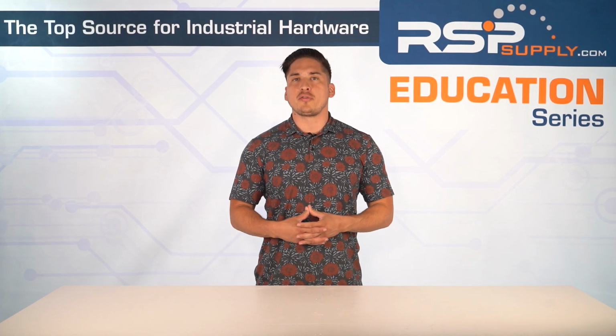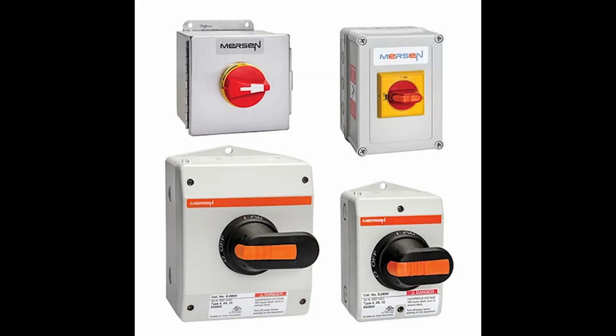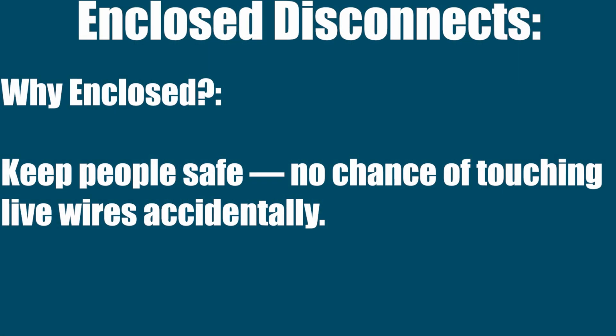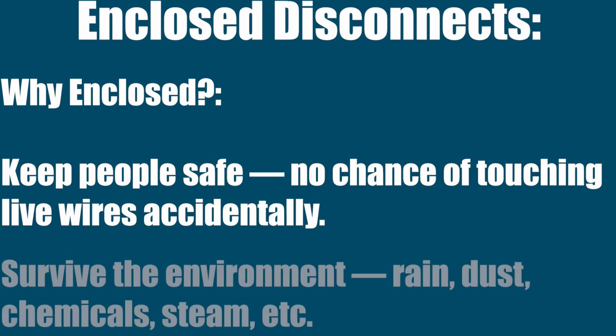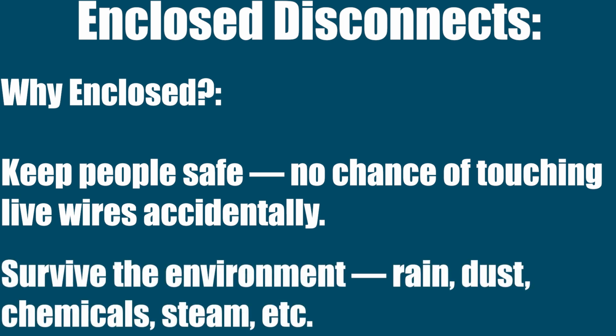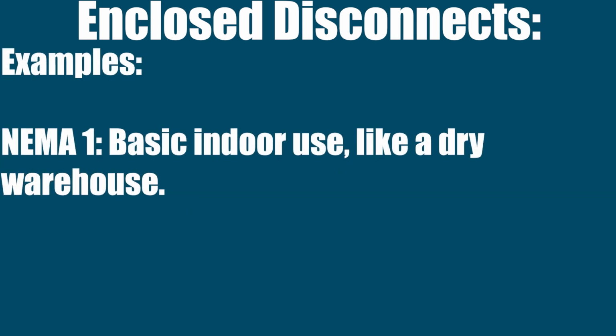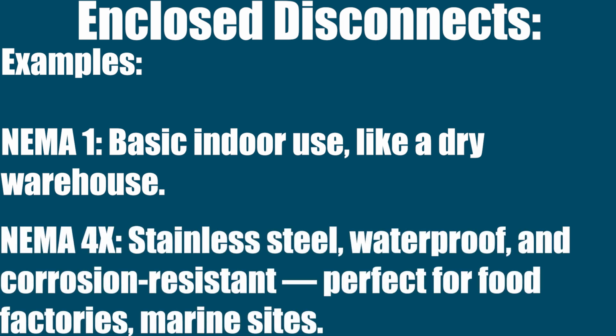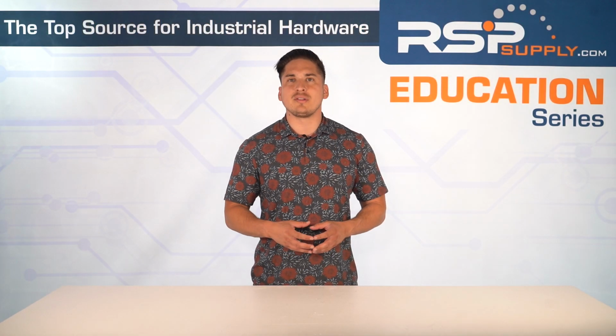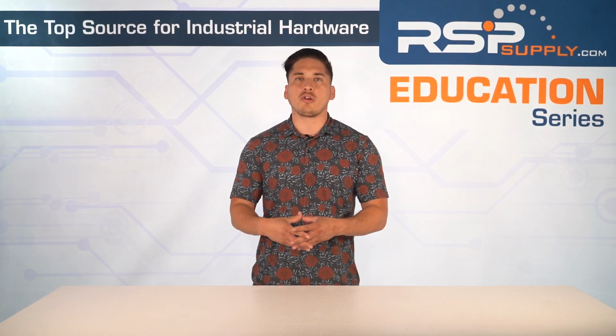So now we're going to talk enclosed versus open frame. Enclosed disconnects, these are boxed up switches that have weather and dust protection, commonly rated with NEMA codes. Why enclosed? It keeps people safe. No chance of touching live wires accidentally. It also is to survive the environment: rain, dust, chemicals, steam, etc. Some examples: NEMA 1, basic indoor use like a dry warehouse. NEMA 4X, that's on the other end of the spectrum. That's a stainless steel, waterproof and corrosion resistant model. Perfect for food factories, marine sites, etc. Best used in standalone disconnects out on a factory floor or in harsh environments.